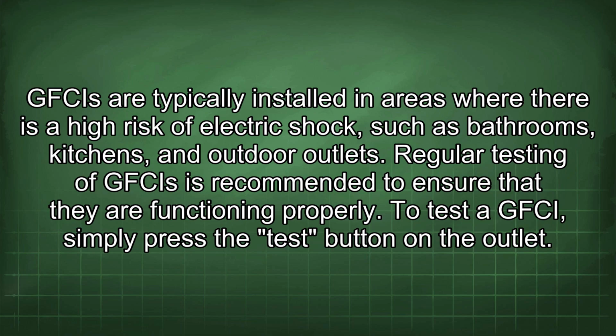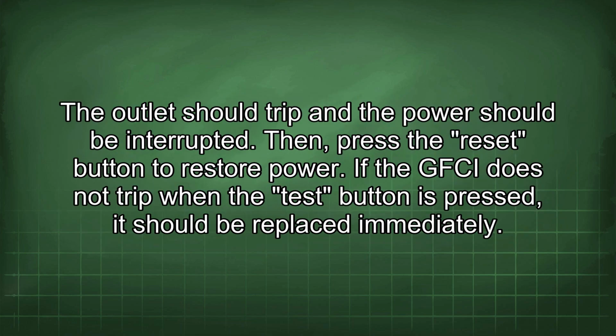Regular testing of GFCIs is recommended to ensure that they are functioning properly. To test a GFCI, simply press the test button on the outlet. The outlet should trip and the power should be interrupted. Then press the reset button to restore power. If the GFCI does not trip when the test button is pressed, it should be replaced immediately.